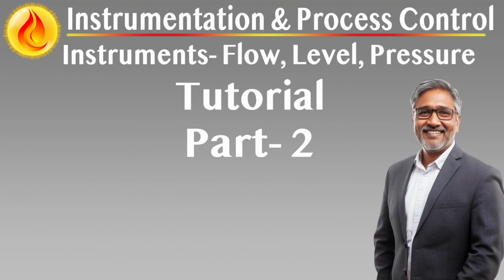Field instrument deployment for operational integrity and lifecycle maintainability. Preference for transmitters over discrete switches. Wherever analog or digital data is required for control, indication, or diagnostics, 4 to 20 milliamp transmitters are preferred over discrete field-mounted switches. Transmitters offer lower failure rates, better accuracy, and enable condition-based maintenance via signal analysis. Direct-mounted switches, e.g. pressure switches, are only permitted with principal approval and must be justified by application constraints such as cost, legacy system compatibility, or extreme simplicity.